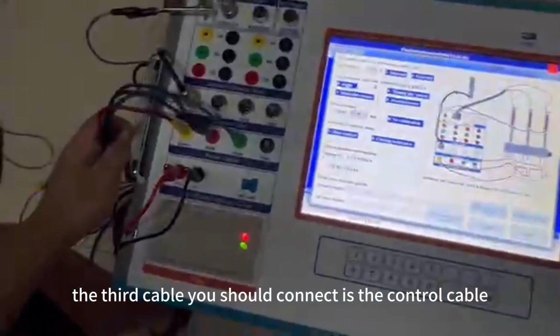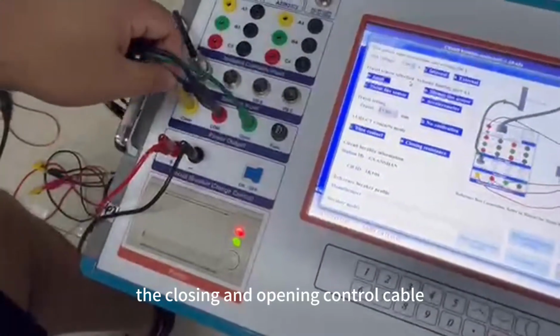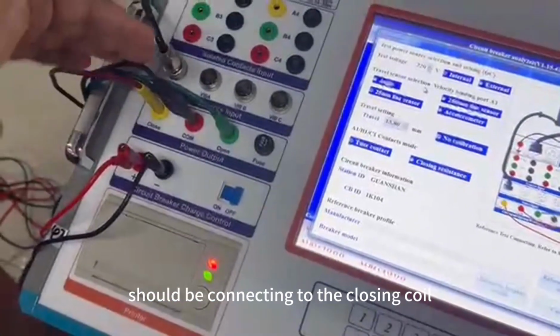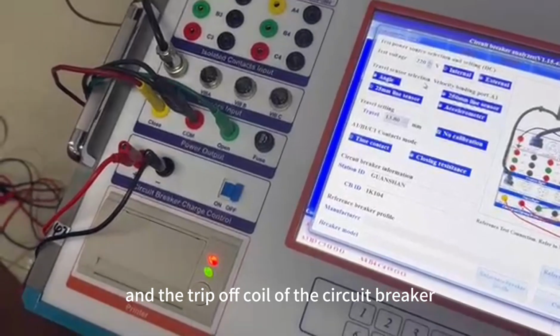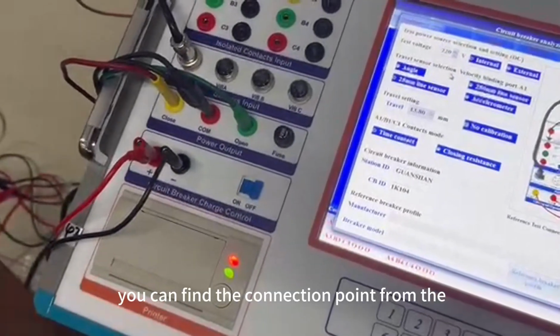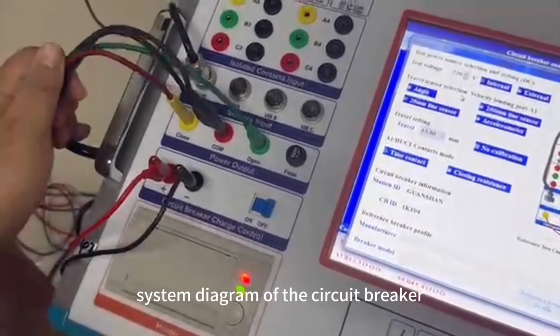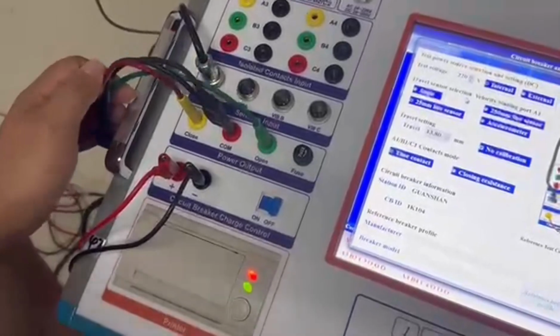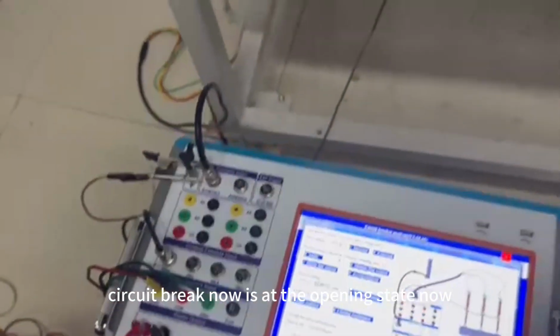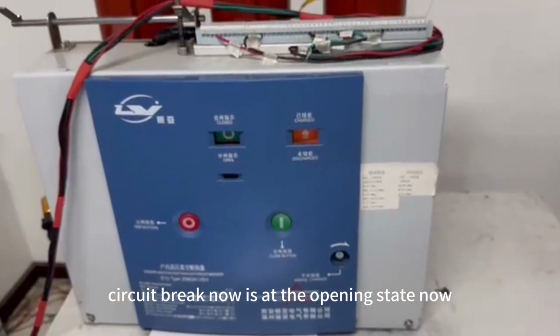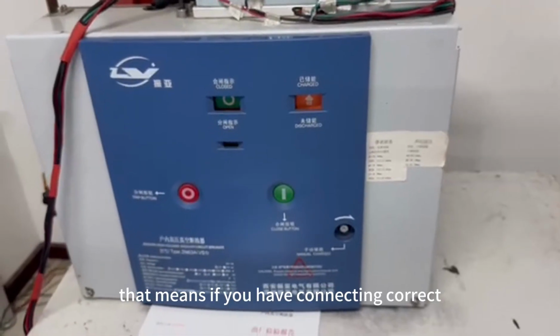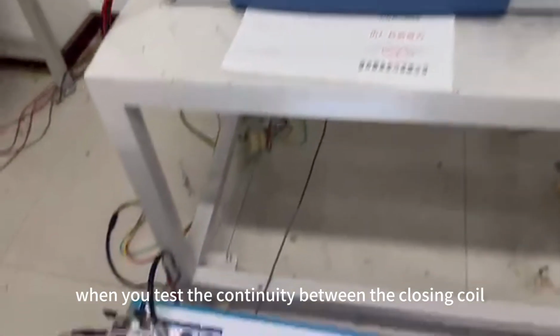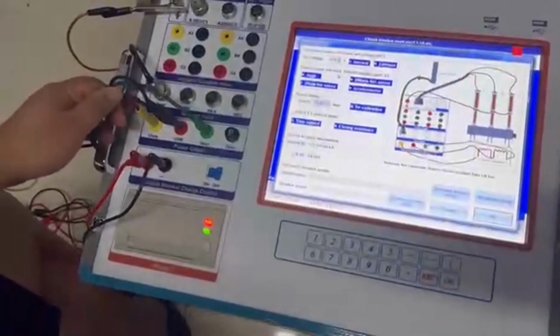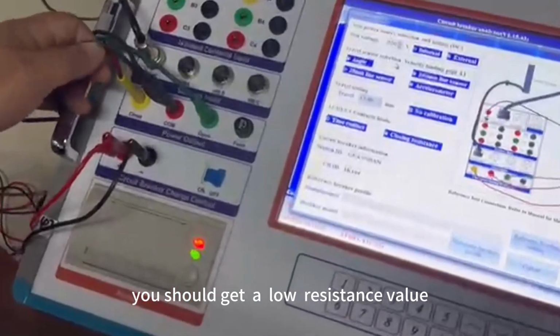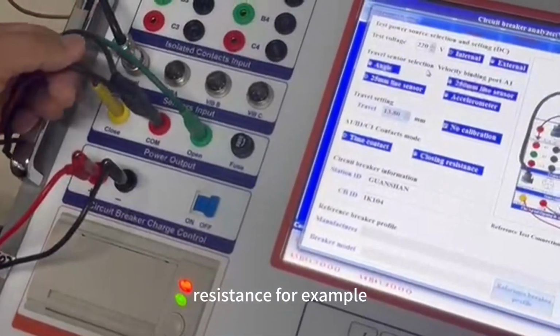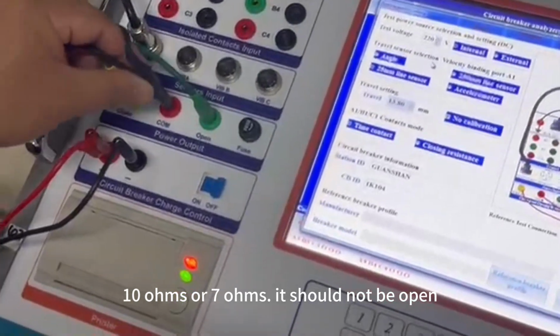The third cable you should connect is the control cable. The closing and opening control cables should be connected to the closing coil and the tripping coil of the circuit breaker. You can find the connection points from the system diagram of the circuit breaker. For example, this circuit breaker is now in the opening state. That means if you have connected correctly, when you test the continuity of the closing coil, you should get a low winding resistance, for example 10 ohms or 7 ohms. It should not be open.